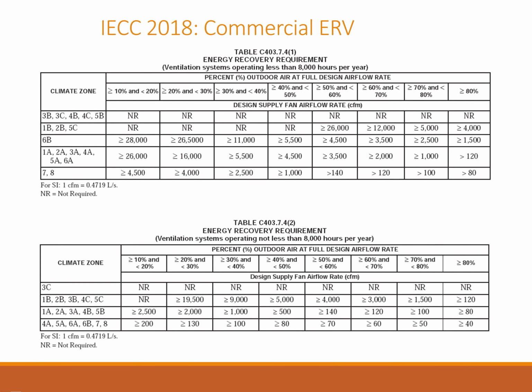Here's an example of two tables from the International Energy Conservation Code, which references the ASHRAE Standard 90.1. The code has different requirements based on ventilation systems operating less than 8,000 hours per year, which is located in the top table. The bottom table shows requirements for ventilation systems operating over 8,000 hours per year, such as buildings that are open 24 hours a day and 7 days a week. The chart represents when an ERV will be required by climate zone, the amount of ventilation or outside air as a percentage of the HVAC system's total airflow, and total CFM by volume.